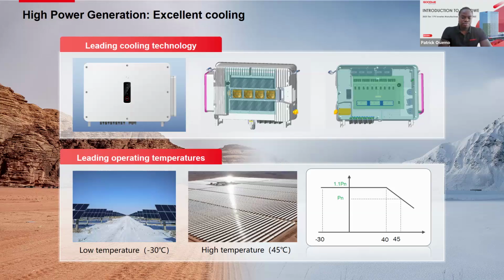This allows you to operate at additional generating capacity. For example, if your temperatures are below 45 degrees, then yeah, you have additional, let me say, overloading capacity. If your temperature is below 40 degrees, then you have even more than 10% additional generation from your inverter. When I say 10% additional, let's say you've installed a 100 kilowatt GT, temperatures below 40, then your 100 kilowatt will be outputting 110 kilowatts, so 10% extra.